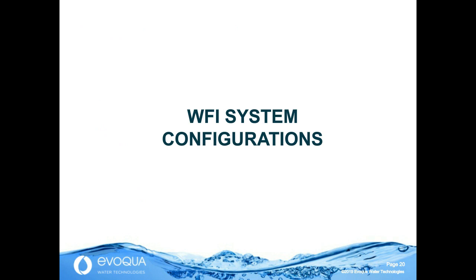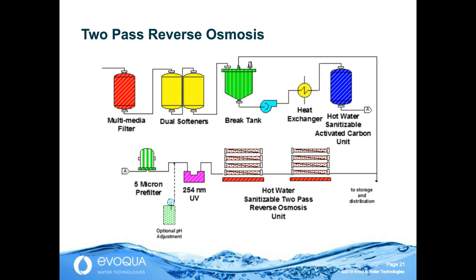Here, two-pass or product-staged reverse osmosis. Years ago, when the terminal process under USP was limited to distillation or RO, several of these systems went in. And here we have softening for scale control. We have activated carbon, the most common dechlorination method upstream of RO. It could be sulfite injection or chemical injection or ultraviolet light, but hot water sanitizable carbon is the most common, and then two passes of reverse osmosis.